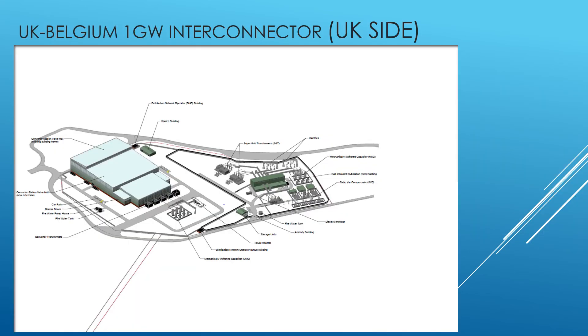This slide shows the UK side of the UK-Belgium 1 gigawatt interconnector. As you can see, on the left hand side there is a converter station, which we can call a DC station, connected to an AIS compound which has a few transformers, a GIS substation, and an SVC, which is ultimately connected to a subsea cable going towards Belgium.